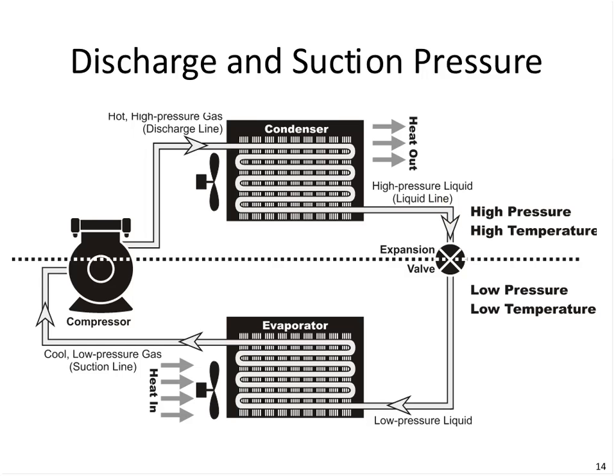Often we call this the high side or high temperature side. The refrigerant under pressure then would be metered through some type of an orifice. Here it says an expansion valve. Sometimes that's a needle valve, and it would fluctuate. There are various types of valves here, but the primary purpose of this valve is to regulate the flow of the liquid refrigerant at the rate that would match the cooling effect that we want here in the evaporator. As a pressure reduction occurs, and it does occur because the compressor is increasing the pressure leaving the compressor, it's also reducing the pressure or pulling on this side of the system.